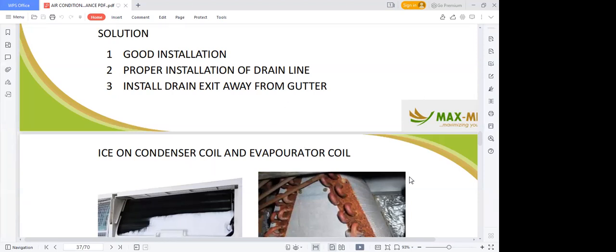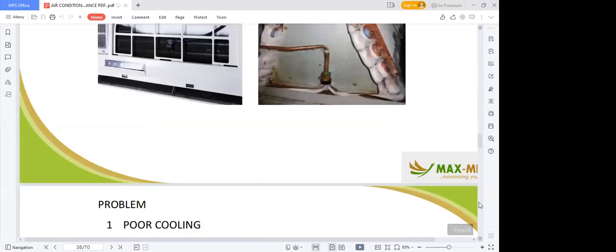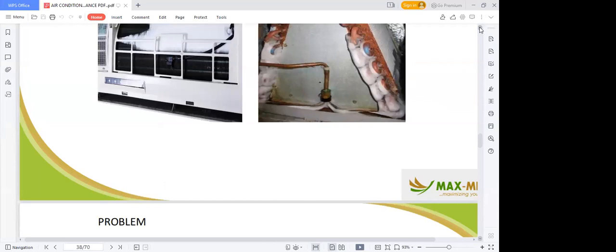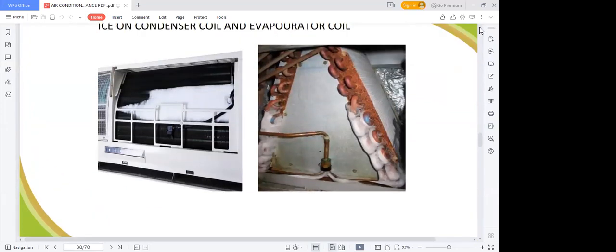Watch for ice on the condenser coil and evaporator coil. This is also a common issue with most of our units. You see ice forming on it. This one is lack of maintenance, or sometimes low refrigerant can cause it. So I will give you a good and clearer example. This unit is designed to take a particular quantity of cool air away from itself. But along the way, there's a blockage. That blockage does not allow it to go out.